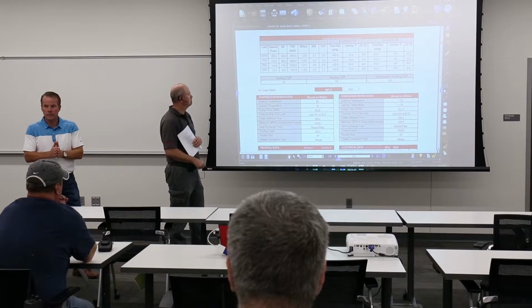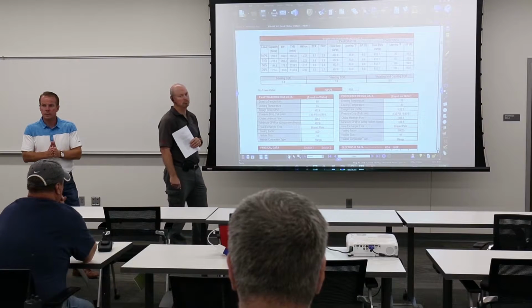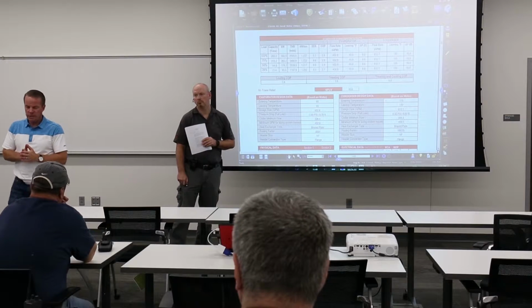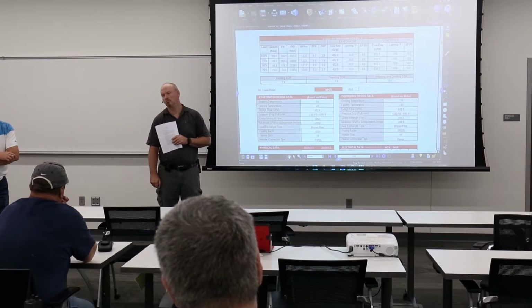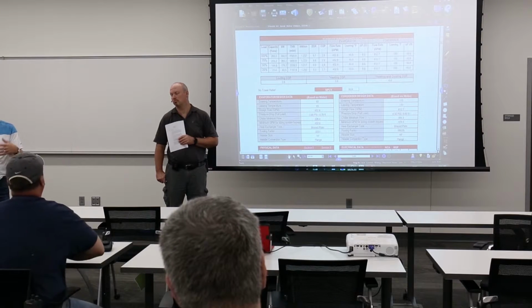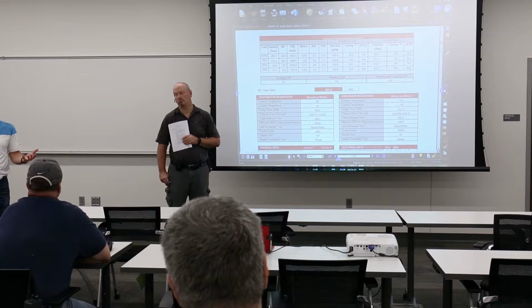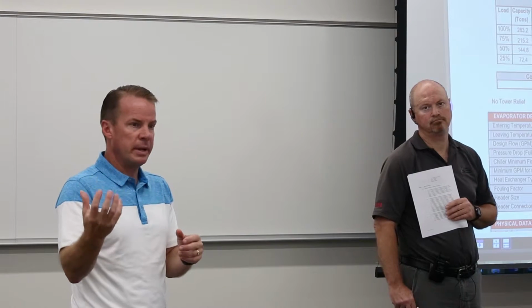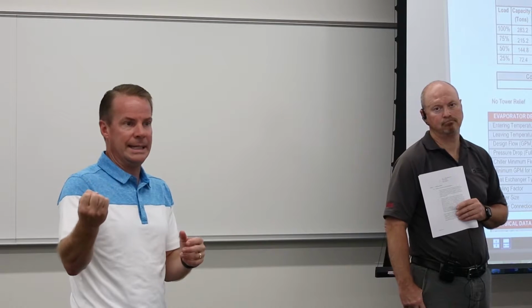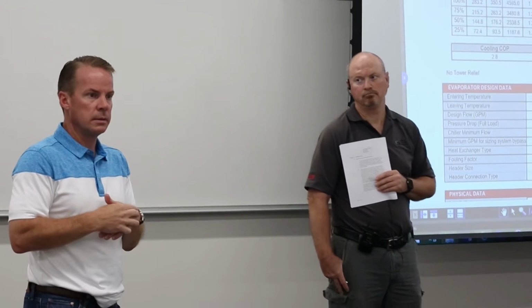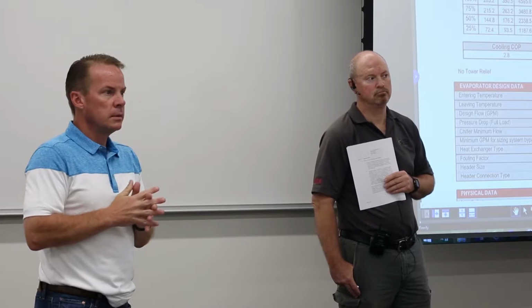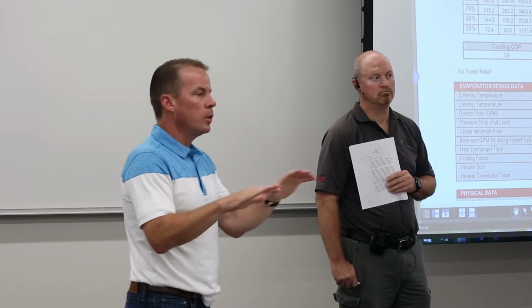And at the times it's not being used for heating, then we have a heat exchanger for our heating water? Yeah, when it's not being used for heating and you have campus chilled water available, it should just be idle. It's going to come on based upon the need for heat. So it's actually going to help our reheat. That's the whole intent of it, it's for your reheat system. Maybe you use steam in a converter to make hot water.